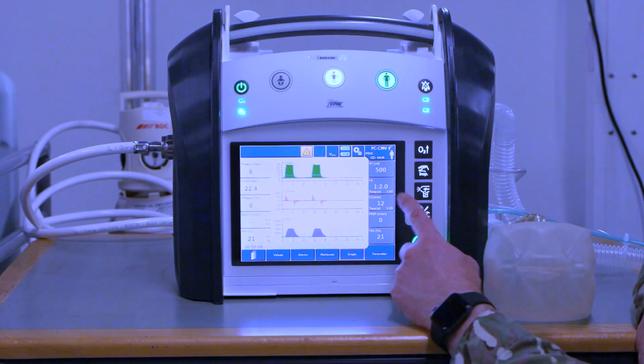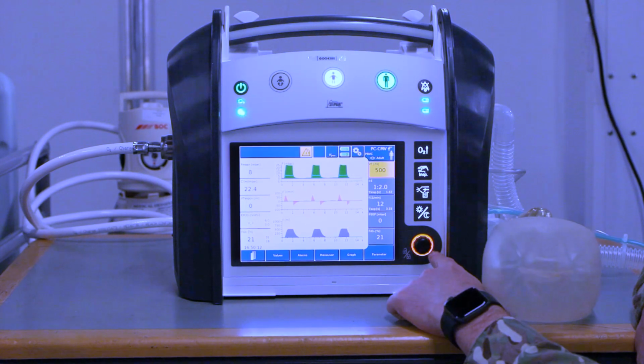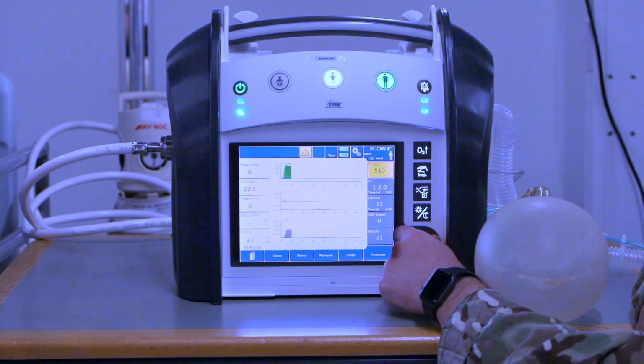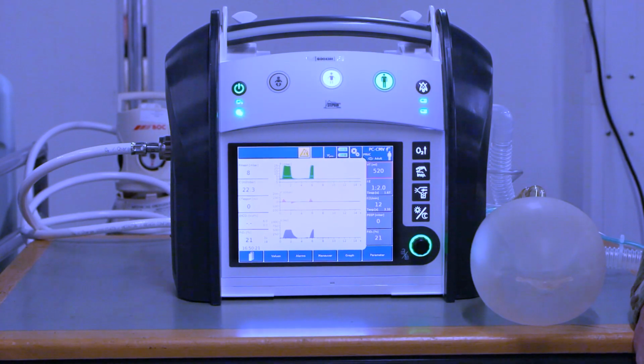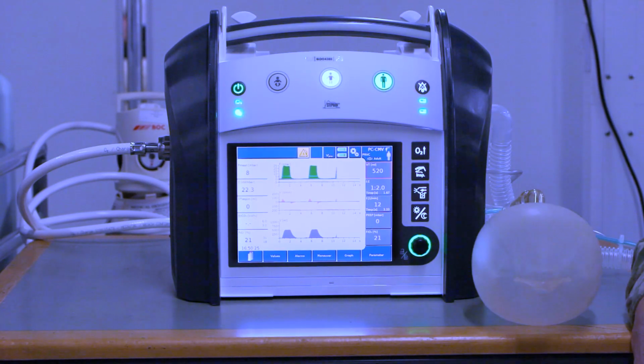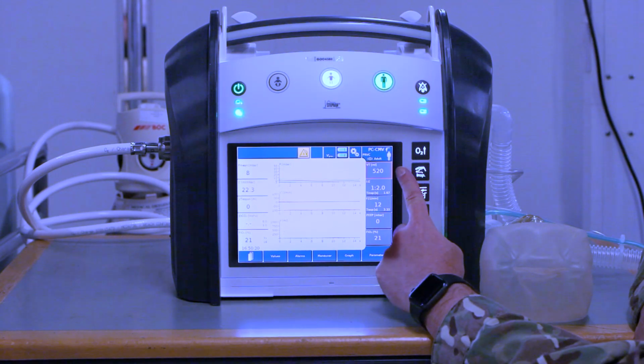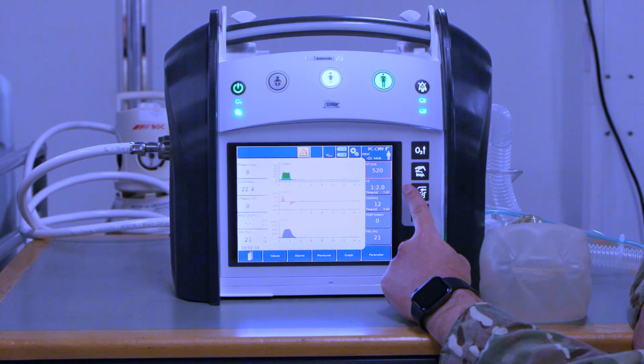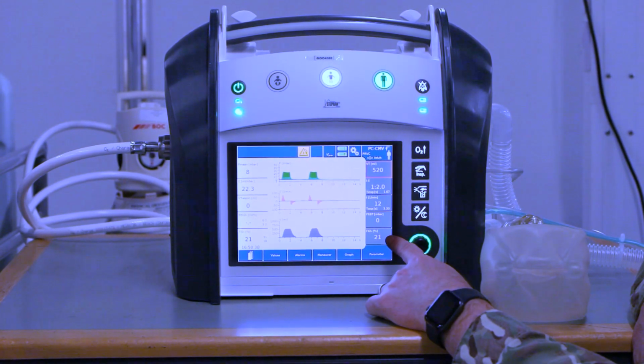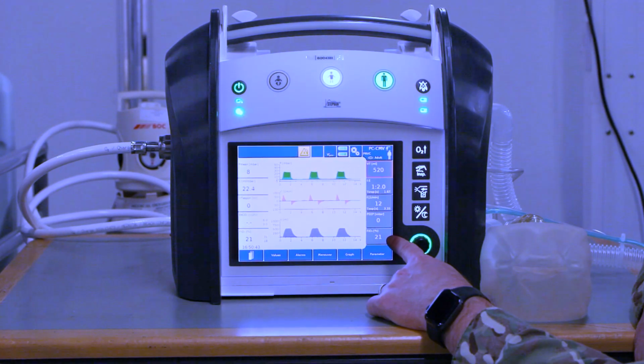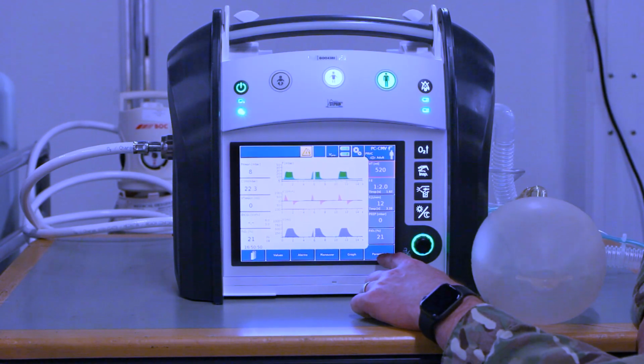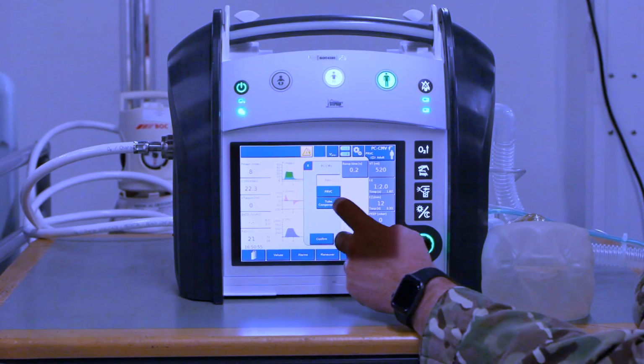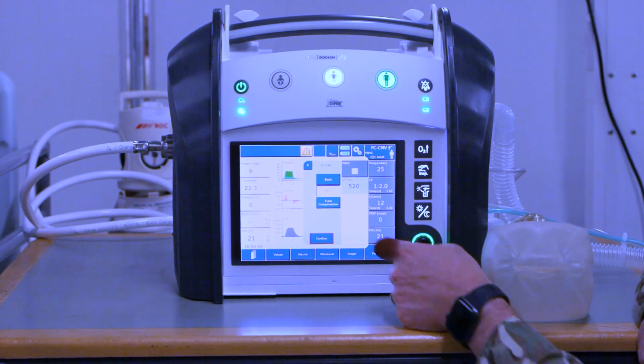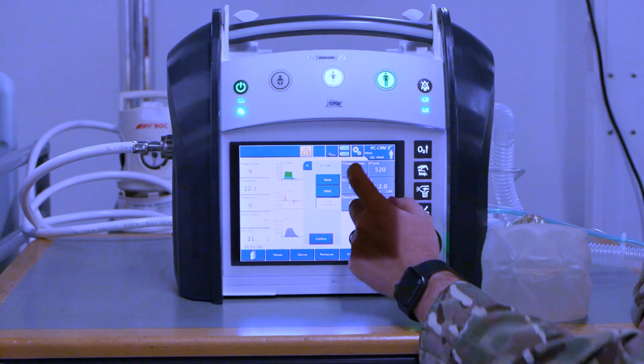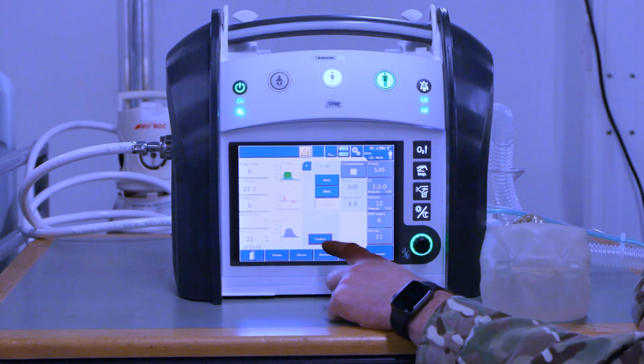On the right hand side of the screen are all these set values by the user. You can click on them. This then changes the knob to an orange colour. This can then be changed, and then it must be confirmed by clicking the button to ensure that has been changed sufficiently, and this will then go green to confirm that change. This will include things like tidal volume or peak pressure, inspiratory-expiratory ratios, frequency, PEEP, and if using high flow oxygen, this will give you the FiO2 that is being set by the user. If you want to alter further parameters, click on the parameter button at the bottom, and this will give you more options, which includes things like pressure regulated volume control, which can be toggled on or off, and tube compensation if wanting to be turned on or off. Again, this must be confirmed by either pressing the knob here or pressing the confirm button.